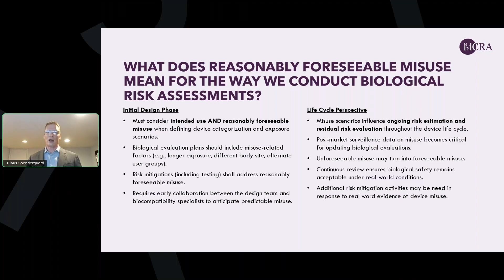Similarly, on the post-market side, biocompatibility already should be something that you're considering throughout the lifetime of the device, but that also gets expanded to this concept of reasonable foreseeable misuse, where you have to look at what is coming back from the field. What is the real world data telling us about how our device is being used? Is it being used in a way that is no longer aligned with the assumptions we made during the initial design phase? Are some of those unforeseeable misuse cases now coming to light to where you could argue that it is now foreseeable misuse? Does that mean that we have to update our biological risk assessment? Are there additional risk mitigation activities that we might have to implement in light of how the device is actually used in the field?